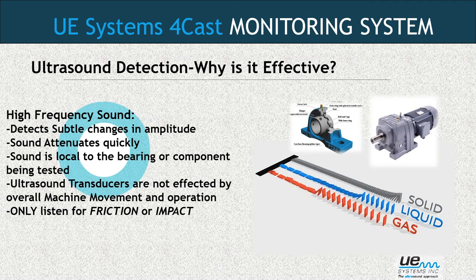The other reason ultrasound is extremely effective is because the sound attenuates very quickly. What that means is the sound where it's being produced, for example, a bearing race, is very strong at the source, but it dissipates very quickly as you move away from the source. So the sound is really local to the specific component that you're trying to test.